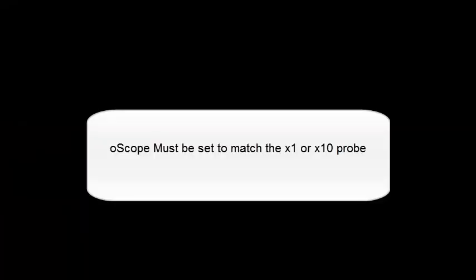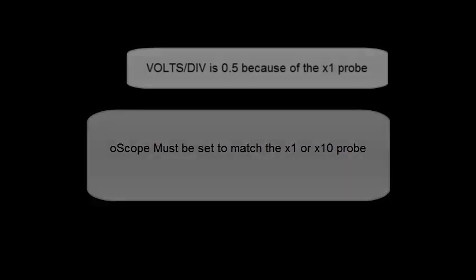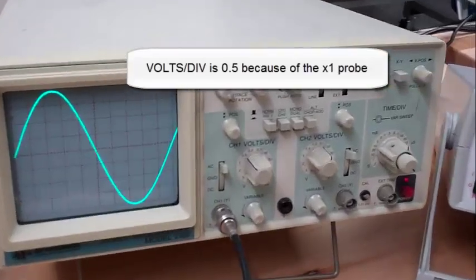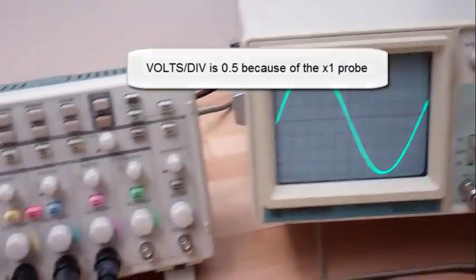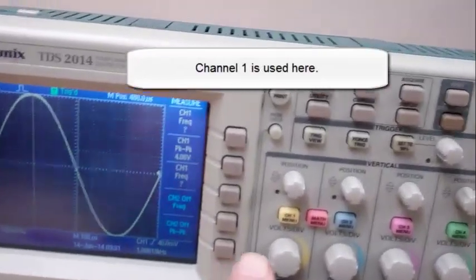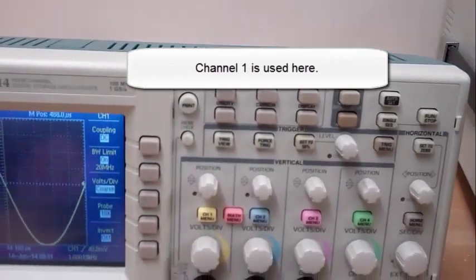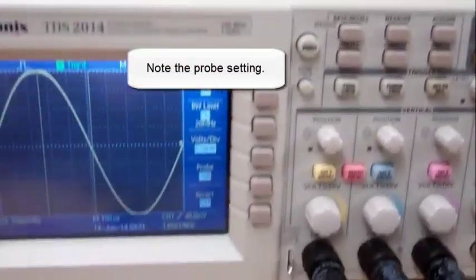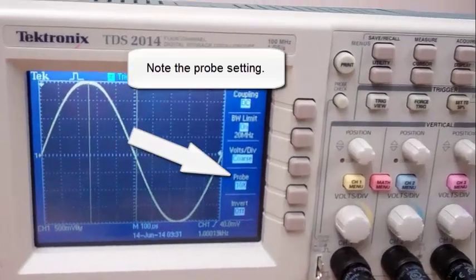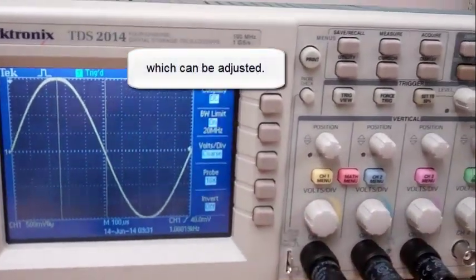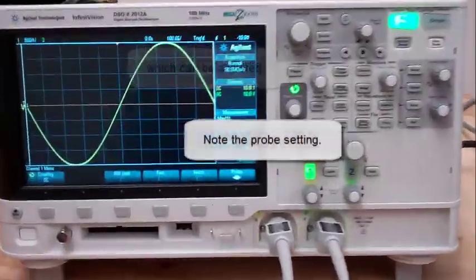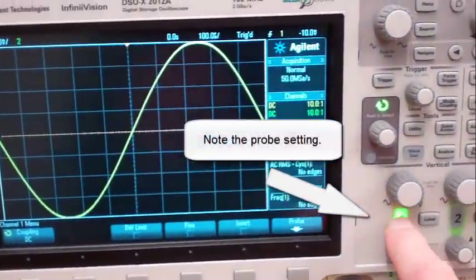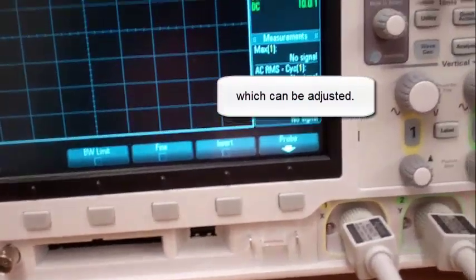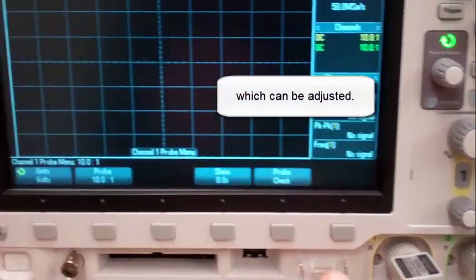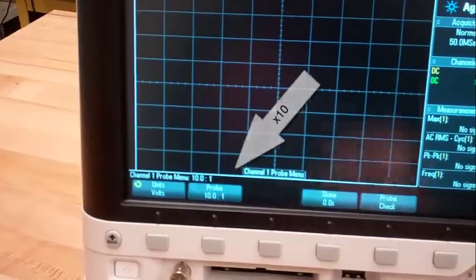The oscilloscope must be set to match the times 1 or times 10 probe. Volts per division is 0.5 because of the times 1 probe, using channel 1. Note the probe setting, which can be adjusted. Note the probe setting here too, which can also be adjusted, currently set at times 10.